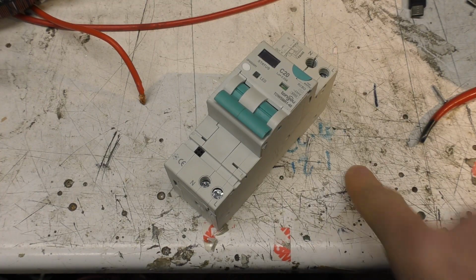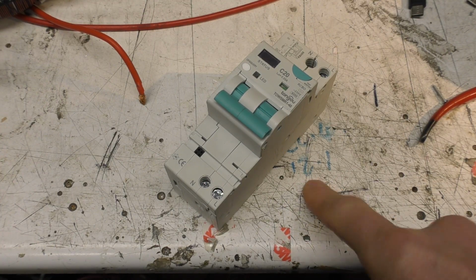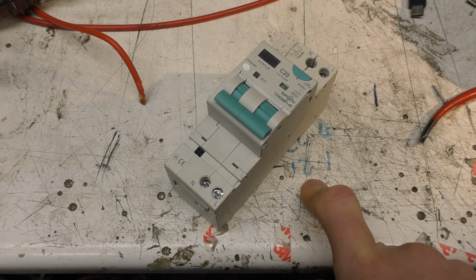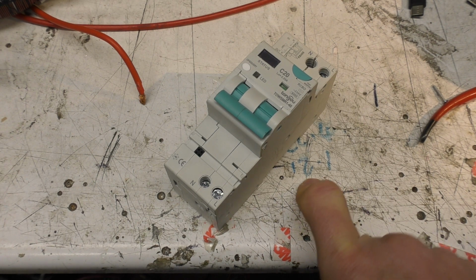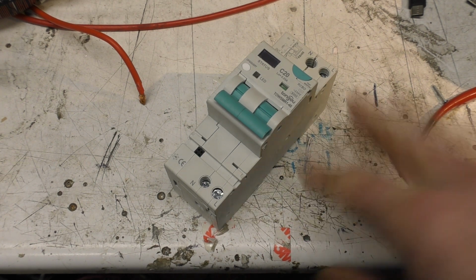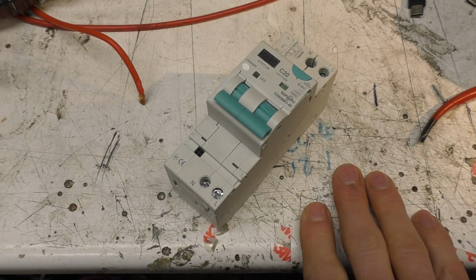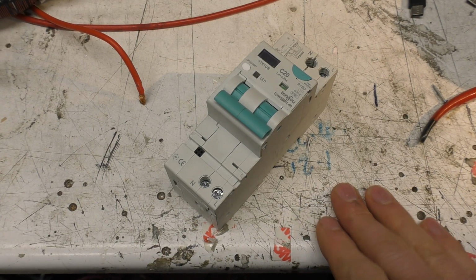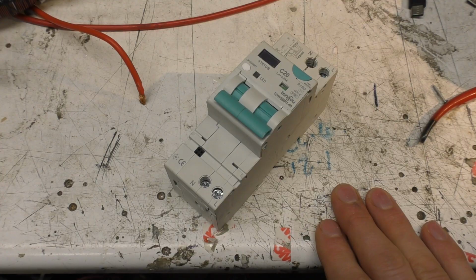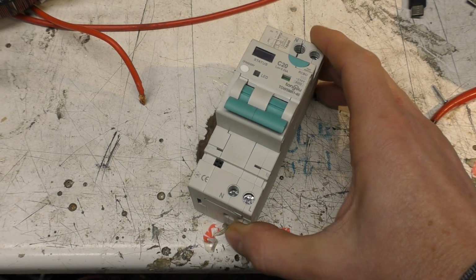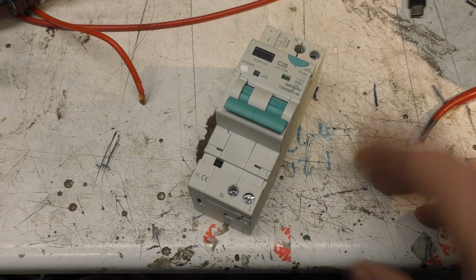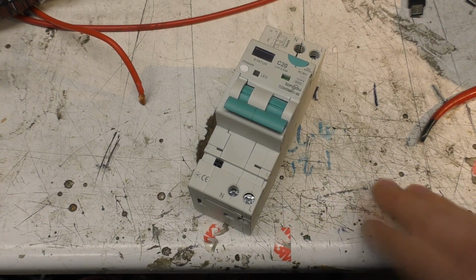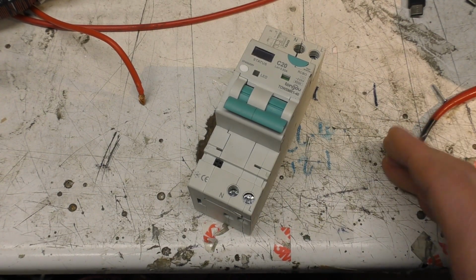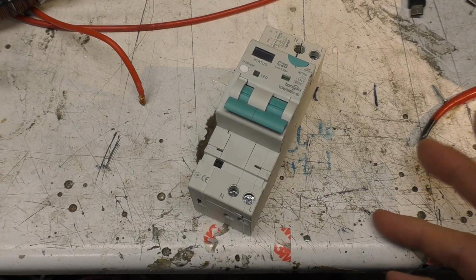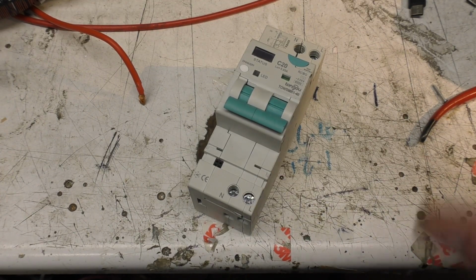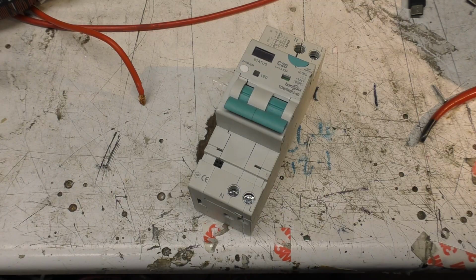Looking at the typical tripping curves, I was running 50 amps through it, and that should have tripped in under 10 seconds. And I've tested it for much longer than that, and it still wasn't tripping. That could be because I only tested that after I'd taken it apart, but just looking at how far that strip was bending, I suspect it may be a 32 amp breaker, and then they use the software electronics to get the lower rating and the adjustability. But overall the build quality looks fine. It's just the concept is completely wrong and stupid, on a number of counts.